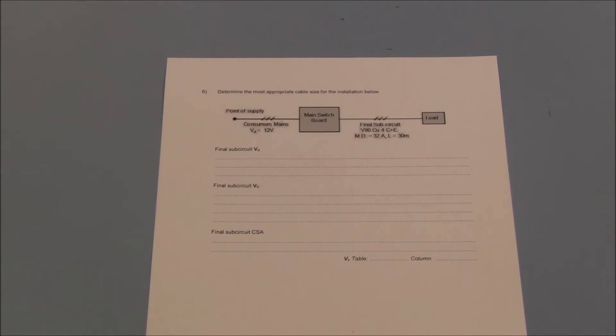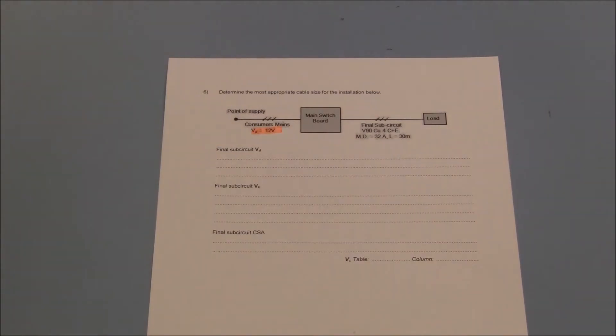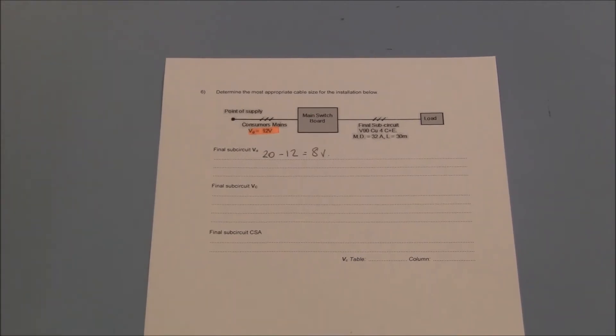This exercise is to select the appropriate cable size of a circuit when you are aware of the maximum permissible voltage drop. This three-phase installation has an established voltage drop of 12 volts across a consumer's mains. This means that the maximum permissible voltage drop across a final sub-circuit is 8 volts.